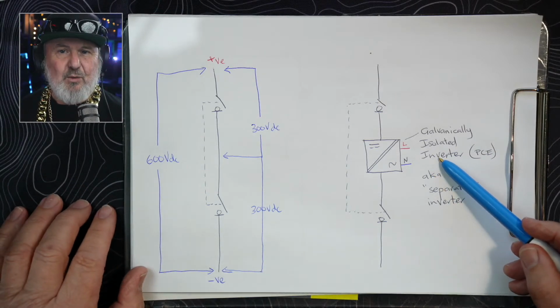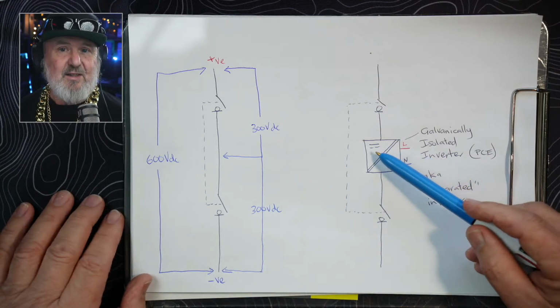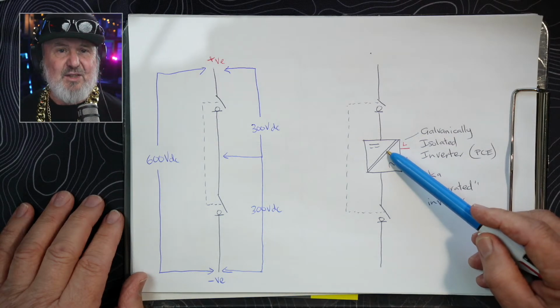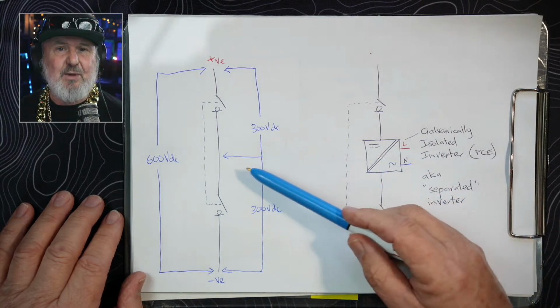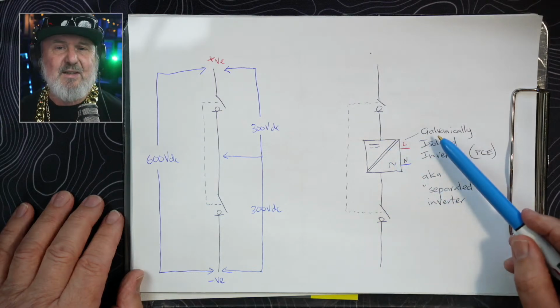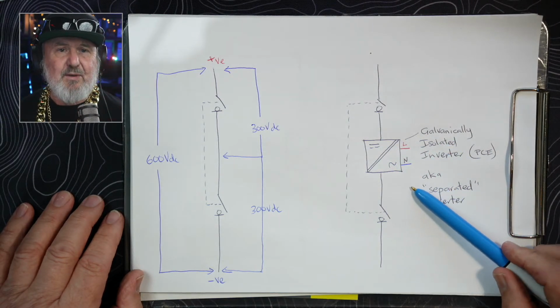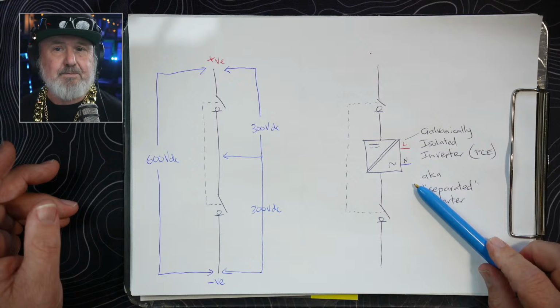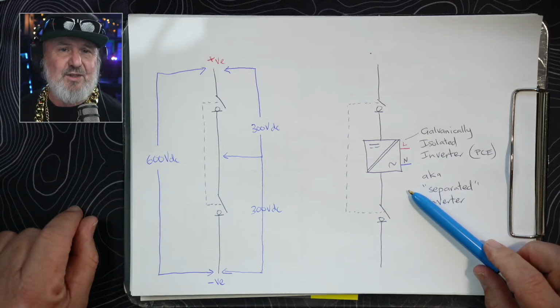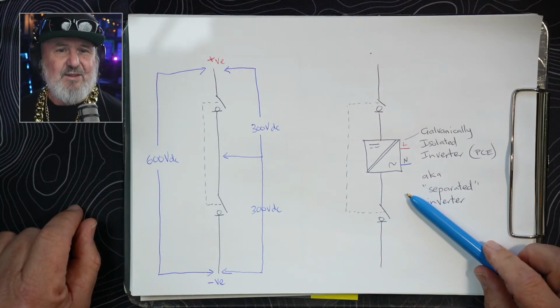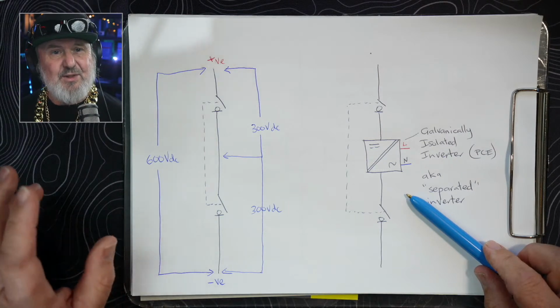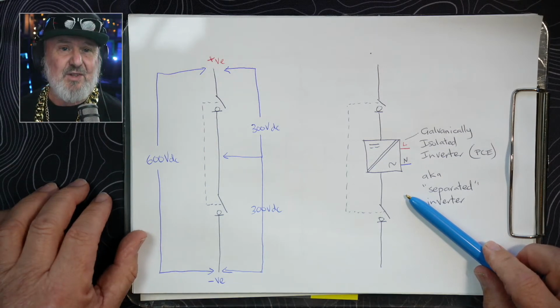And you need to be able to isolate an inverter from its energy source, in this case a PV array, so we'll have a PV array connected. It's not drawn here yet. We need to be able to isolate that PV array for both maintenance and safety, and also under fault conditions. So if something goes wrong and you need to remove that inverter, you need to do it safely, not with the fault current passing through it.